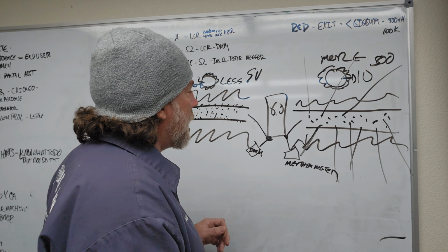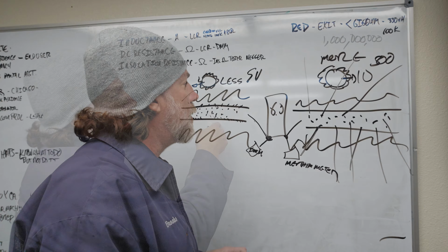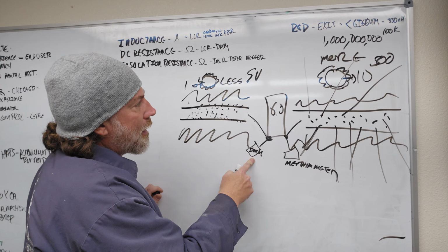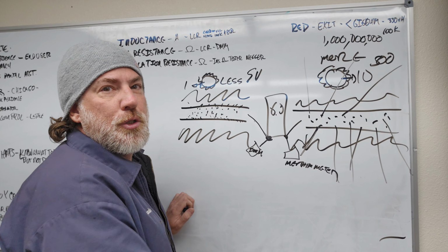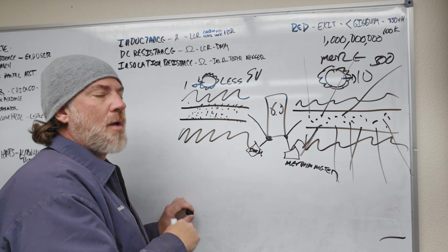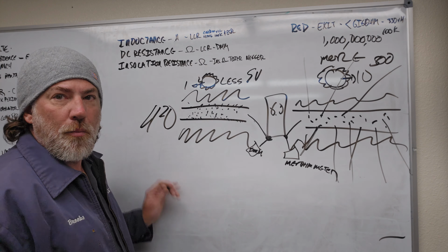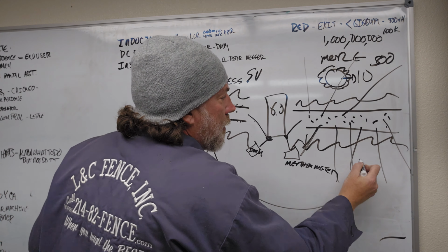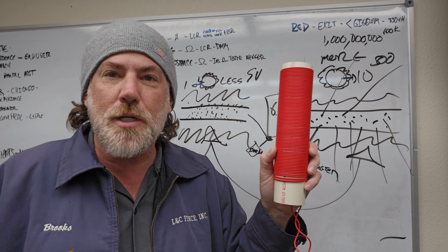That is what our test will actually show, is that there's electricity flowing, and it'll show 20 megohms or below that, or whatever the case may be. And if not, then it'll show higher, 40, 50, 60 megohms, up to what we've documented here, above a gigohm. Low pressure, you may not ever actually see anything with your DMM because it's not putting out enough electrical pressure. High pressure, electricity shoots out, hits the concrete, hits the rebar, hits the earth ground, and then goes over. This is why it's so important to actually wet the loop with H2O. You need to put water on here and you need to put water on here. And that is the ability to see if there is damage in the insulation.